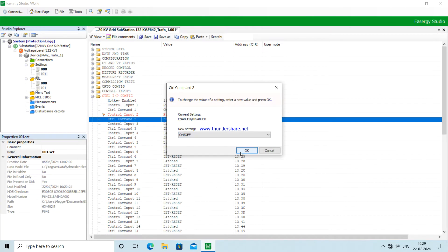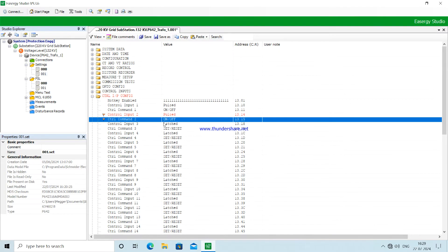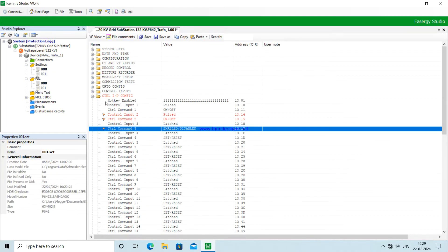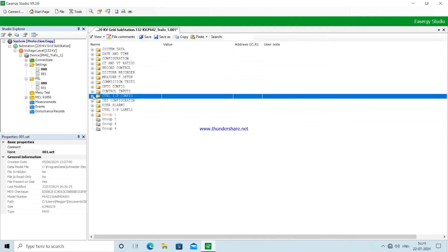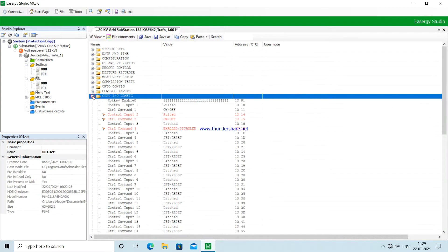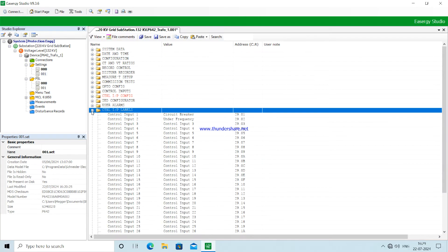For control input one and two we have used the pulse command, and for control input three we have used the enabled and disabled command because it will be latched either in enabled condition or in disabled condition. For breakers it should be pulsed because continuous output should not be given to breakers or isolators where there are actuating coils.